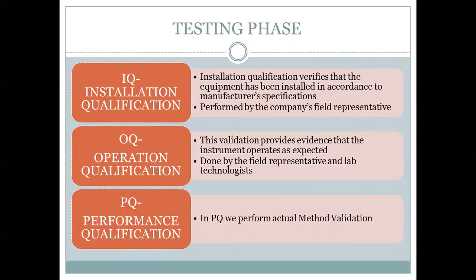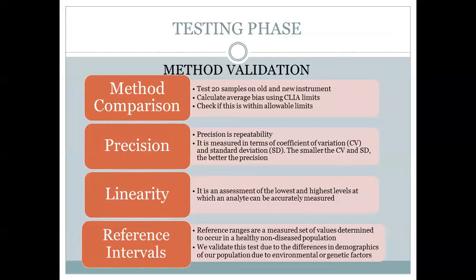And in performance qualification, we perform the method validation. We validate the method of the tests. We have four method validation processes. We compare the methods between our new instrument and our old instrument to make sure that our new instrument is not giving us very wrong or erroneous results. And there is a whole method to do that.